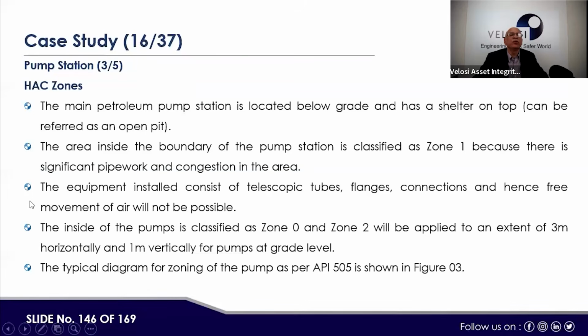Then HAC zone: the main petroleum pump station is located below grade and has a shelter on top, so it can be referred to as an open pit. The area inside the boundary of the pump station is classed as zone 1 because there is significant pipe work and congestion in the area. The equipment installed consists of telescopic tubes, flanges, and connections, and hence free movement of air is not possible. The inside of the pump is classed as zone 0, and zone 2 will be applied to an extent of 3 meters horizontally and 1 meter vertically for the pumps at grade level.